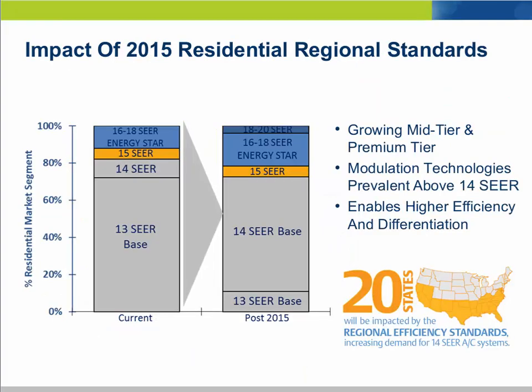If we dive a little bit deeper into the efficiency standards, I'd like to talk first about residential standards. The United States was carved out into three zones with increased efficiency standards. Prior to this, 13 SEER was the requirement across all 50 states. With these new standards, states in both the south and southwest move up to 14 SEER as a new minimum requirement. Modulation may not be required to deliver 14 SEER, but if you look at the graph on the left, there's generally a tiering strategy — a good, better, best strategy — and achieving mid-tier or premium tier systems will certainly benefit from modulation technologies.